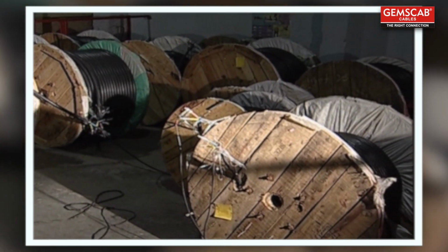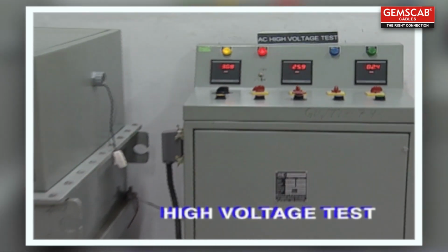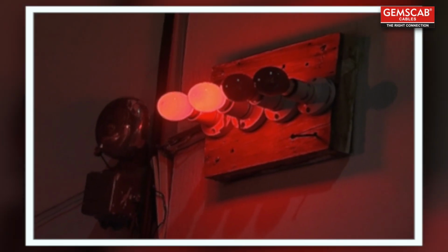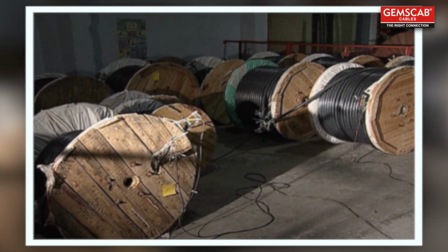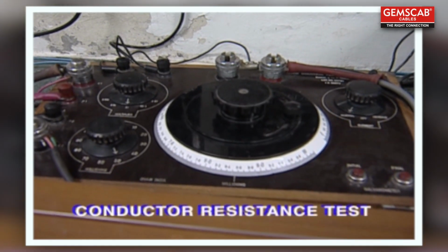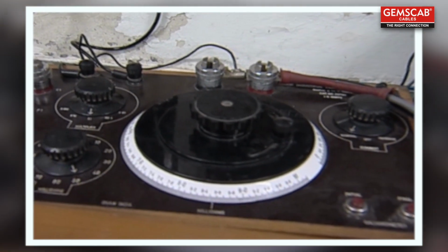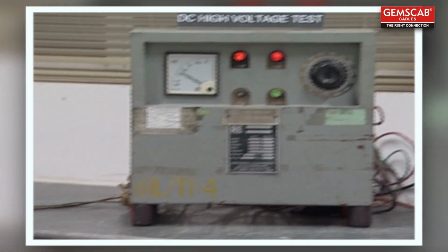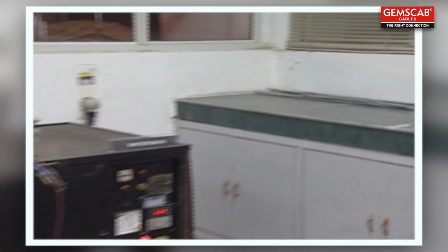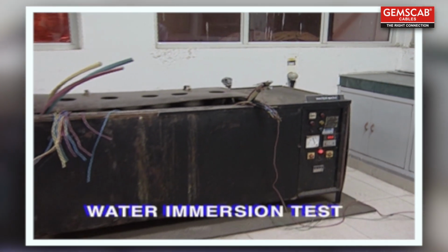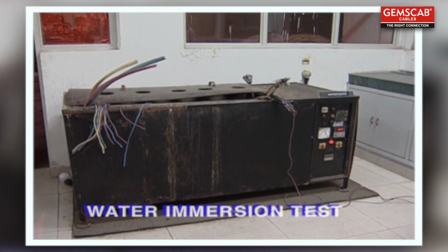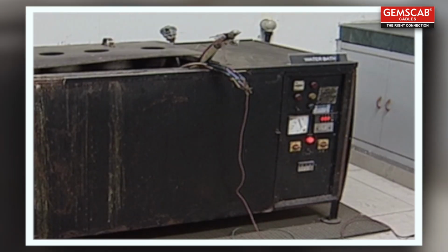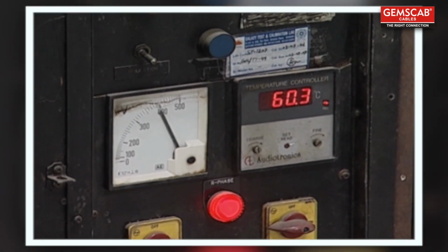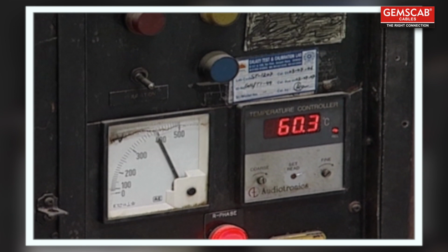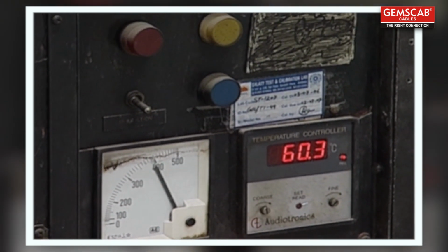Gemscab cables are subjected to a series of stringent post-production tests. Starting with the high voltage test, which follows, is an accelerated test carried out at a higher voltage for a shorter duration. The conductor resistance test checks for specified design requirements. The high voltage or water immersion test tests the ability of conductors to withstand high voltage and elevated temperatures for longer durations. This test checks the influence of the dimension, construction, processing conditions and property of material used in the cable.